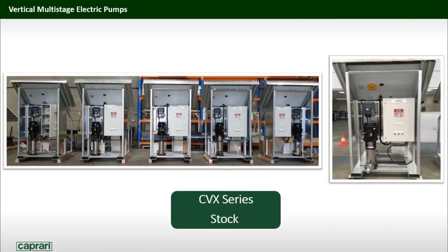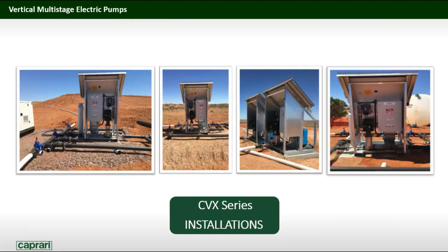The images here show just some examples of Caprari vertical multi-stage CVX series electric pump installations. These are hydraulic parts of various sizes and numbers of stages, appropriately chosen to guarantee the required levels of Q and H. Each cab provides a support surface for the base of its electric pump. Each individual group consists primarily of the hydraulic element, namely the electric pump, on which the electric motor is mounted. The inverter, electrically connected to the motor, is wall mounted in specific cases here. Electric power supply and control of the electric pump unit are done through the control panel.